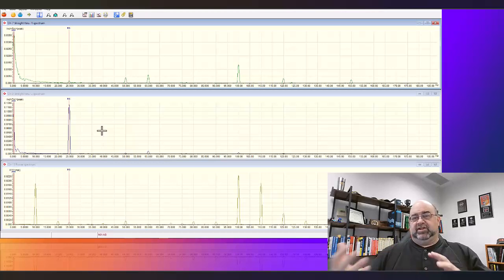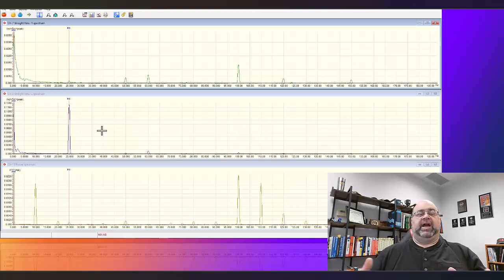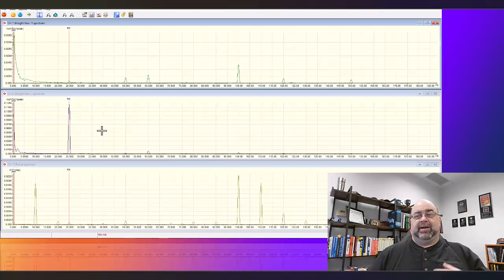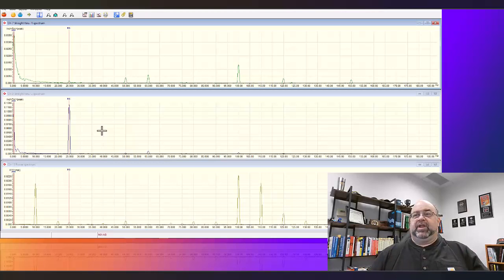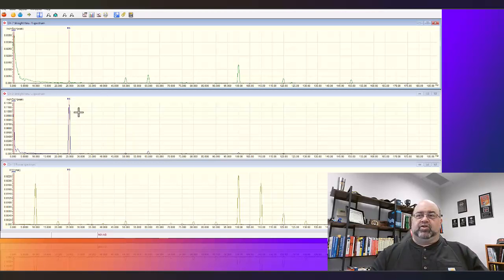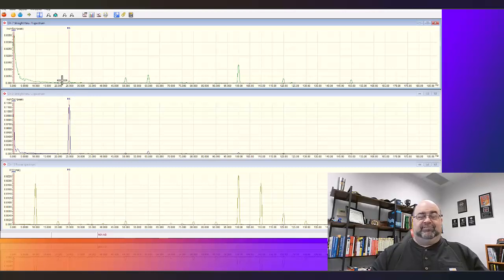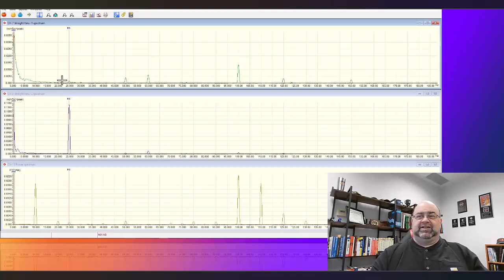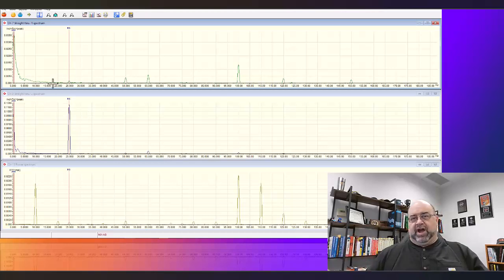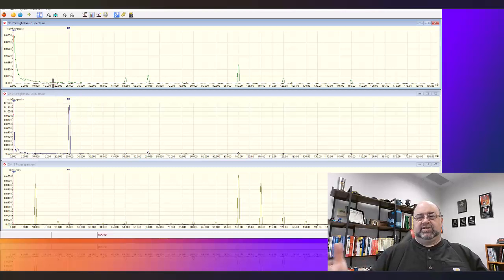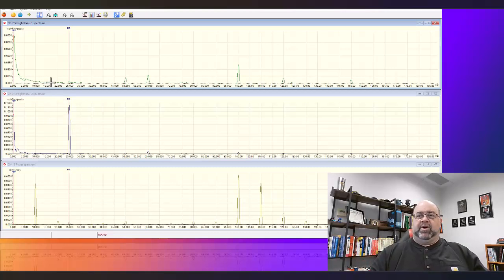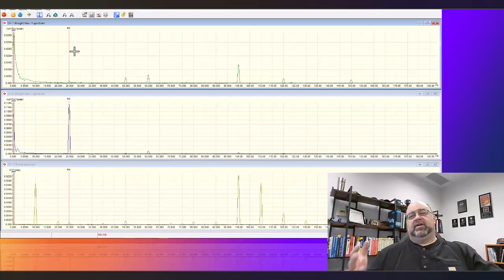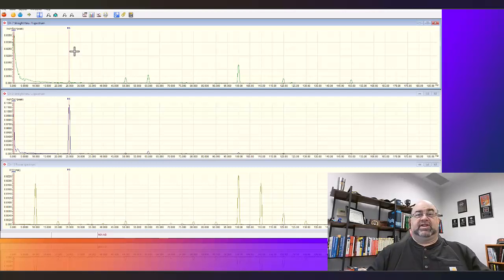I'm going to show you this one and then we're going to apply it real time or as real time as we can get. I'm going to run the calculations separately but here's how we approach just looking at this. Now we're going to make the assumption because we did get virtually identical readings that this is the same on both the drive end and opposite drive end. There is a bearing issue going on but we're going to ignore that, and that's one of the nice things about pulling things out as an FFT.